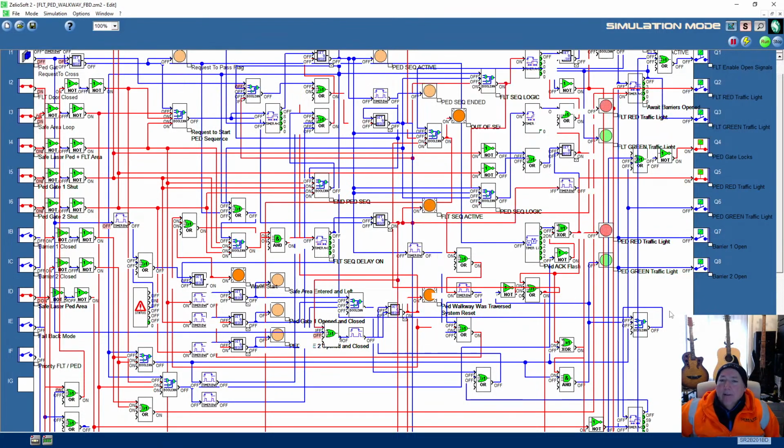Okay, so it's come out of sequence. It's flashing at me and it's about to transfer over. Okay, so at least the flash shows that it's active. Now, if it's a prolonged flash, then you come out of sequence. But if it's a flash during the normal sequence, at least it shows you that you're not waiting in vain for nothing to happen, because one of the systems has failed or whatever. Right, so let's try it the other way this time. Just make sure our override works.